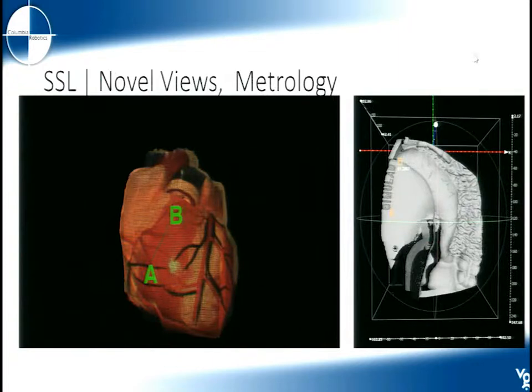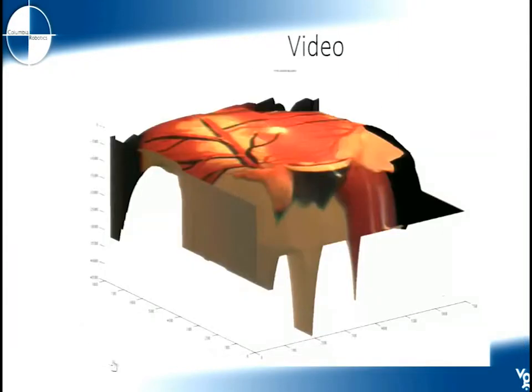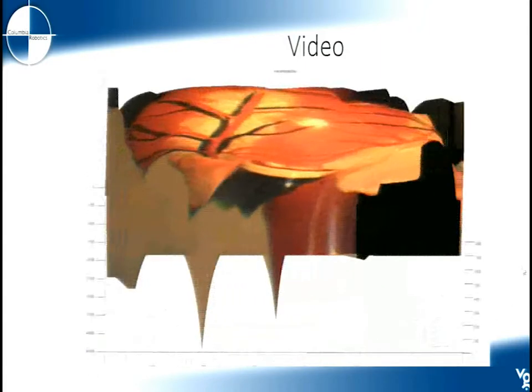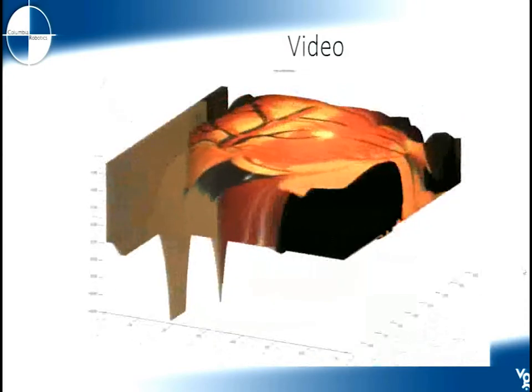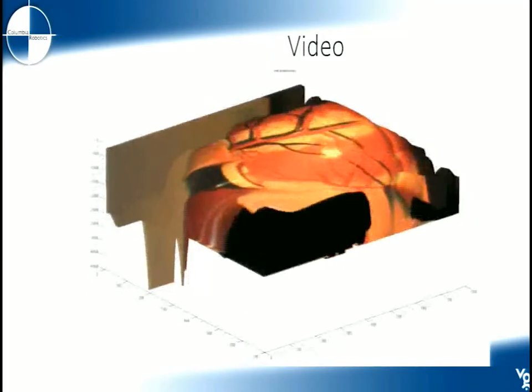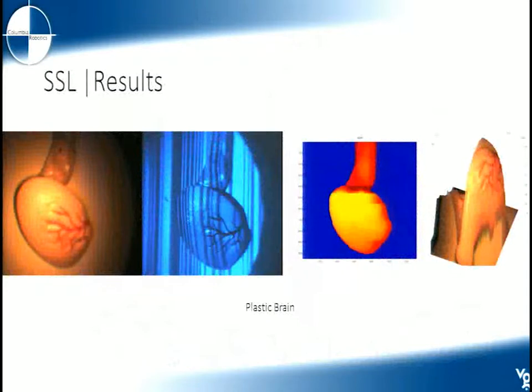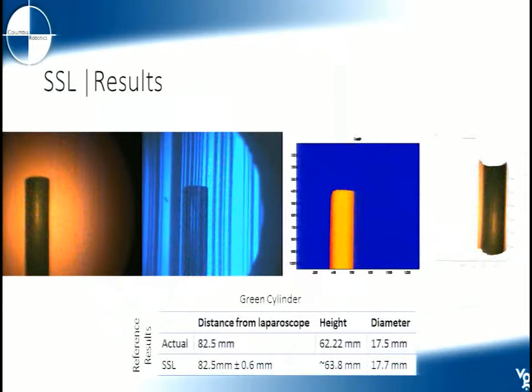The prototype uses two laparoscopes — this could also work as an add-on to a stereo laparoscope. A stripe pattern is projected onto the scene and used with standard structured light ideas to create a depth map, which is then meshed into a 3D model. Texture pixels can be mapped onto the model for a realistic result. We demonstrated reconstruction of plastic organs including a plastic brain, and achieved accuracy within 1 millimeter in distance and 0.2 millimeters in diameter.